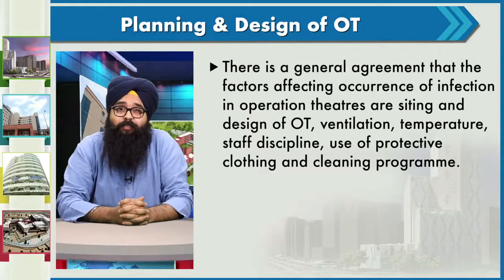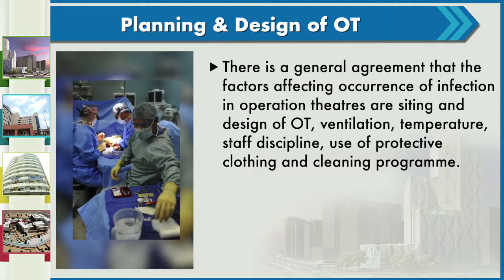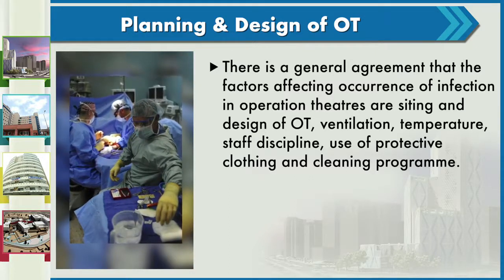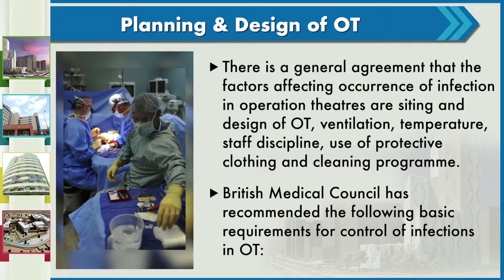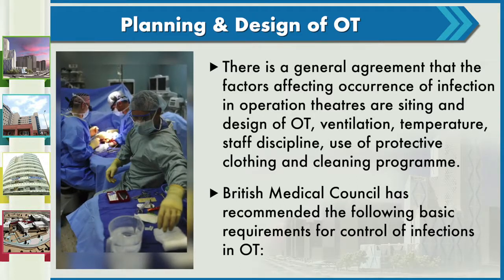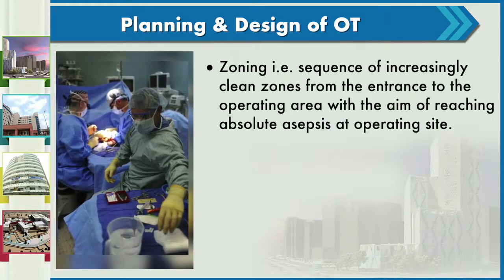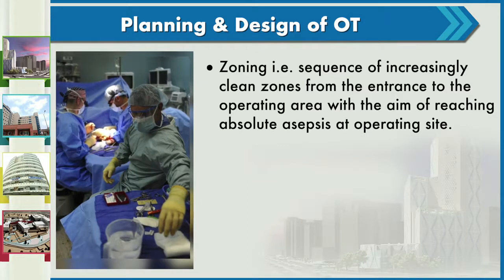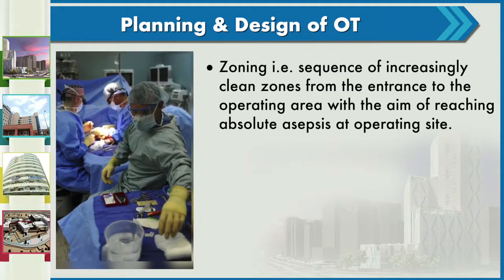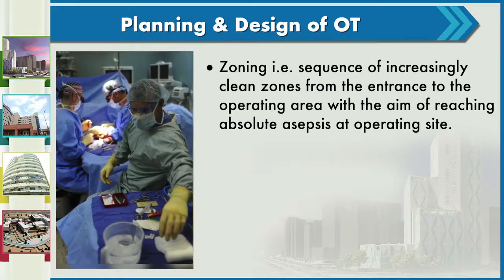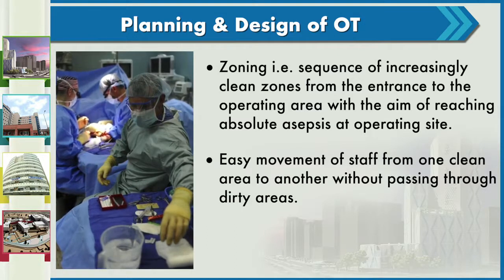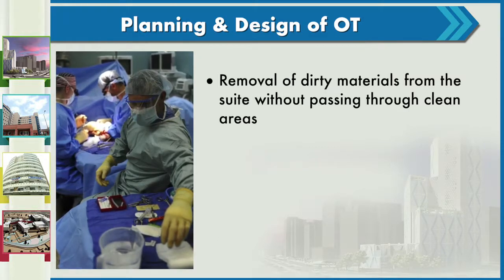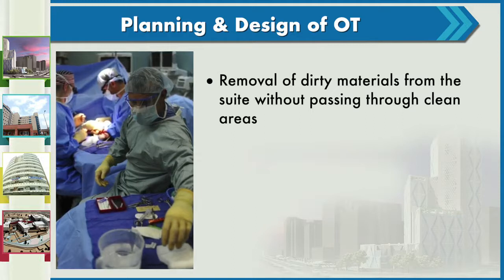Factors affecting occurrence of infection in operation theatres include the design of OT, ventilation, temperature, staff discipline, use of protective clothing, and cleaning program. British Medical Council recommendations include separation from general hospital traffic and air movement, and zoning — a sequence of increasing clean zones from the entrance to the operating area with the aim of reaching absolute asepsis at the operation site. Easy movement from one clean area to another without passing through dirty areas, and removal of dirty materials without passing through clean areas, are also required.